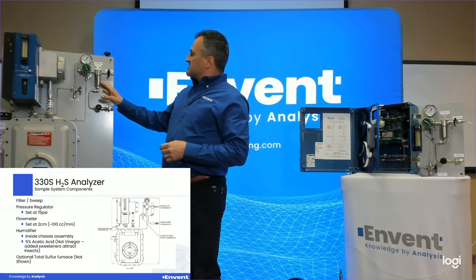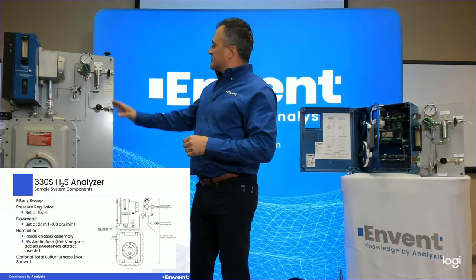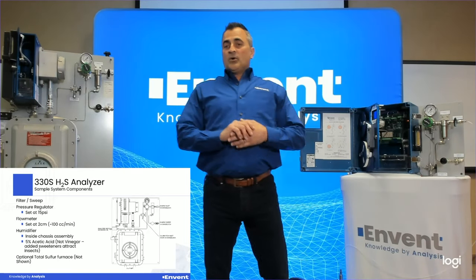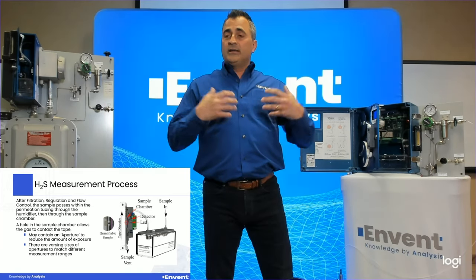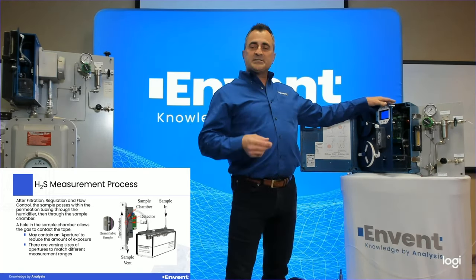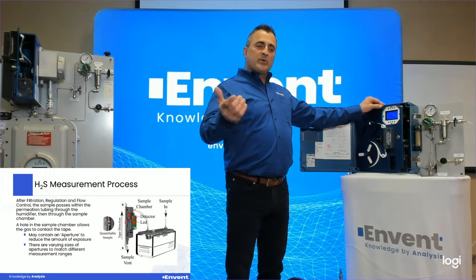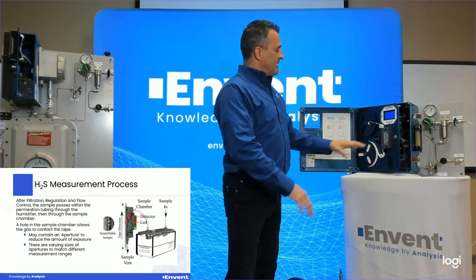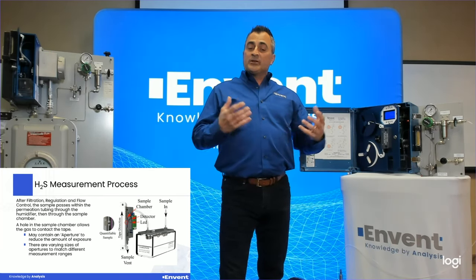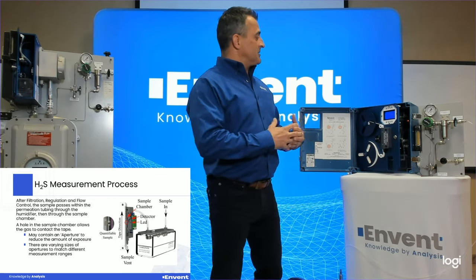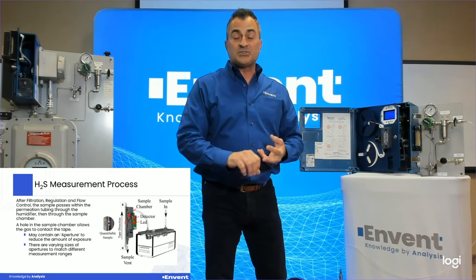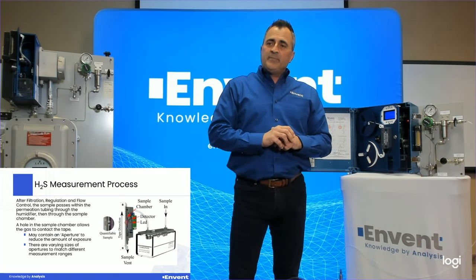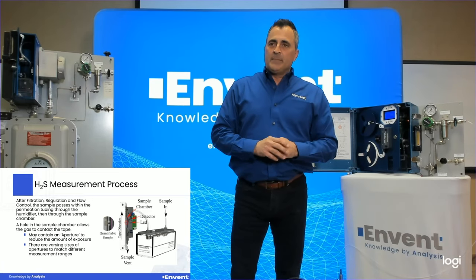The 330 has a very similar sample system with filtration, regulation, flow control, and a humidifier inside the enclosure. The reason we humidify is we need humidified gas going to the tape for proper absorption. Two main reasons: first, you want consistent repeatable readings, which require good absorption on the tape — a chemical reaction takes place when H2S contacts lead acetate tape, turning it brown. With a dry sample you can still stain the tape but you don't get consistent or repeatable readings, and staining takes place much slower.